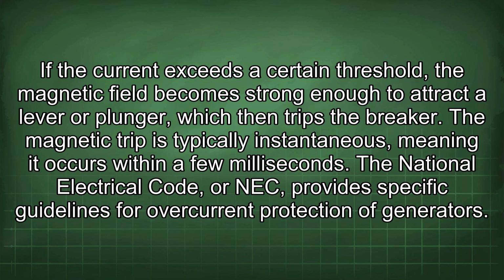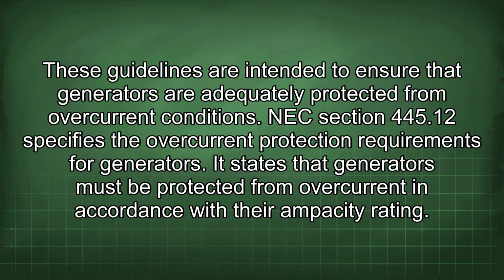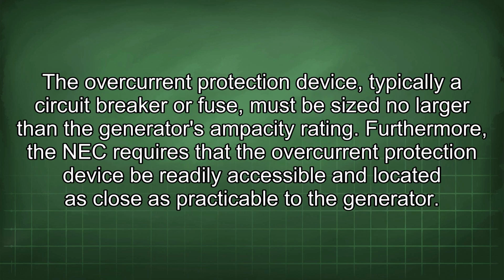The National Electrical Code, or NEC, provides specific guidelines for overcurrent protection of generators. These guidelines are intended to ensure that generators are adequately protected from overcurrent conditions. NEC Section 445.12 specifies the overcurrent protection requirements for generators. It states that generators must be protected from overcurrent in accordance with their ampacity rating. The overcurrent protection device, typically a circuit breaker or fuse, must be sized no larger than the generator's ampacity rating.